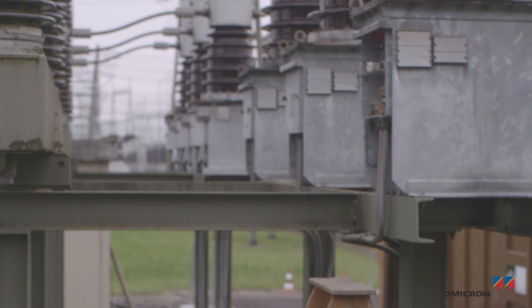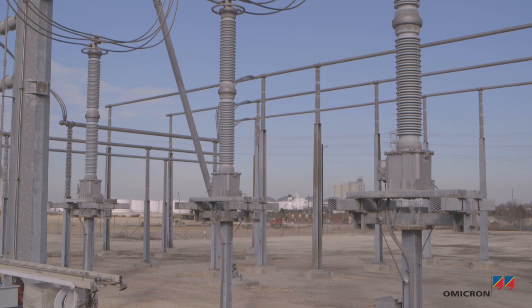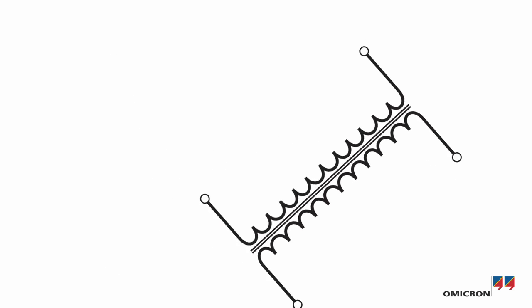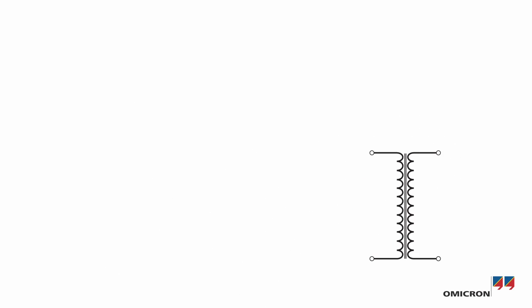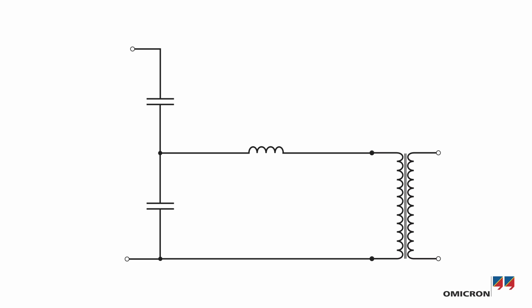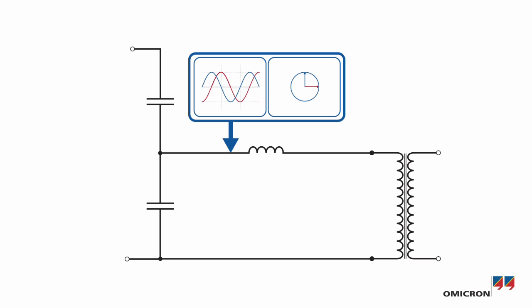The majority of voltage transformers used today are either inductive VTs or capacitive voltage transformers. Capacitive voltage transformers consist of an inductive VT, a high voltage capacitive divider, and a compensating reactor. The compensating reactor is designed to resonate with the primary capacitances at rated frequency, helping to compensate the phase shift due to the high voltage capacitive divider.